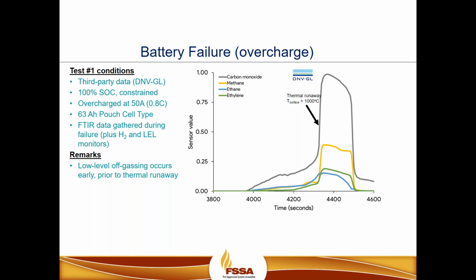And you can see that in the test itself that traditional types of gas sensors would not be able to detect at the lower levels. So early on in the test, before thermal runaway is achieved, there's very little gases, and they're at relatively low levels to be able to detect. Of course, the carbon monoxide with this particular type of battery was most prevalent. However, methane, ethane, and ethylene were present, but they really didn't spike or peak or off gas into the space until thermal runaway was already achieved.